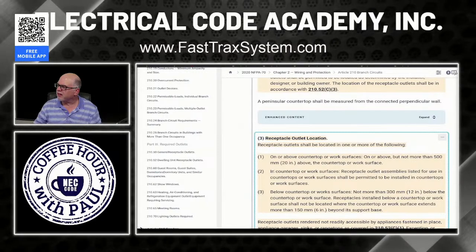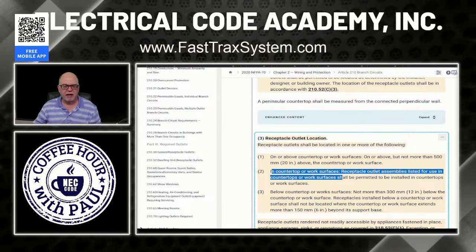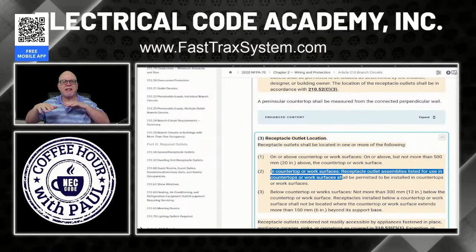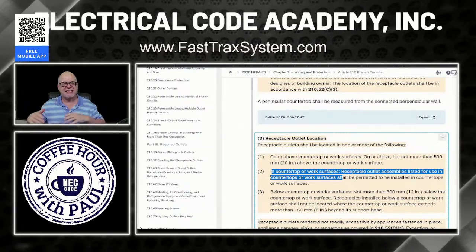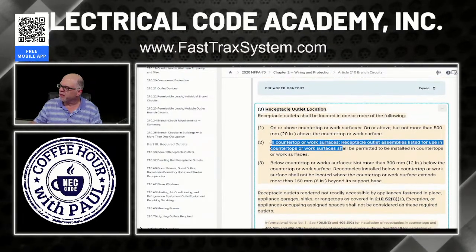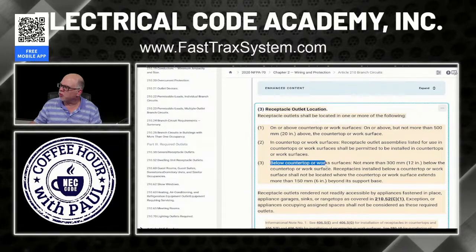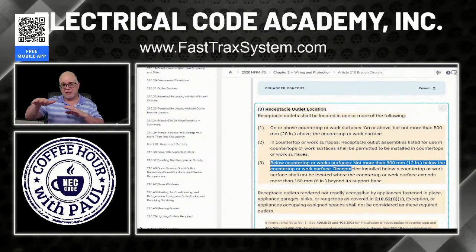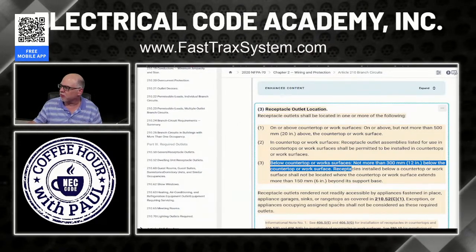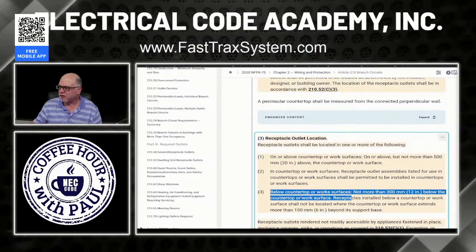Right here, it says in the countertop or work surface, receptacle outlet assembly listed for use in the countertop. That's those pop-up style. It could pop up out of the countertop. In an island, they would take up drawer space, so typically not what we would use, but you could. And then, of course, the third one right here is the one that allows it to be below the surface. And that's what you're going to have on an island. You're going to have to go below the surface. So that's what it talks about here.